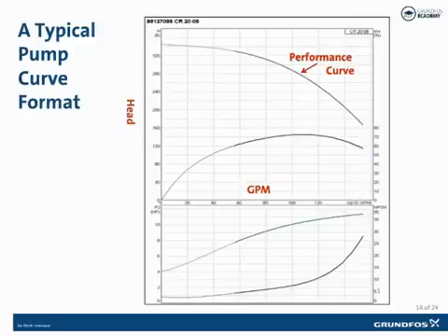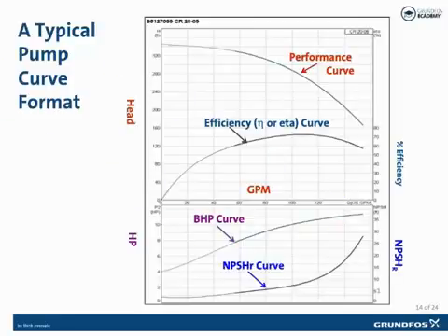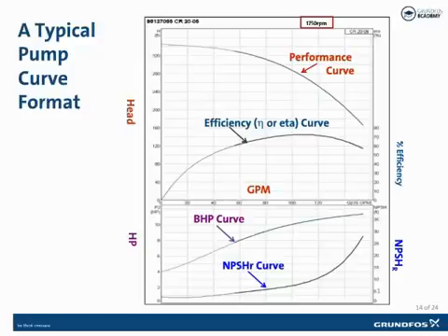Additional curves depicted include pump efficiency, measured as a percentage; brake horsepower, used to select the size of the motor; and the net positive suction head required by the pump in feet. All of these curves are dependent on where the pump is currently operating. Most HVAC pumps operate at a nominal speed of 1,750 RPMs, which is the speed of a 4-pole motor. If higher pressures are required, a 2-pole or nominal 3,450 RPM motor may be desirable. Occasionally, 6- or 8-pole motors may be used when high flow and low head is desirable. All of these factors are critical to the pump system designer.